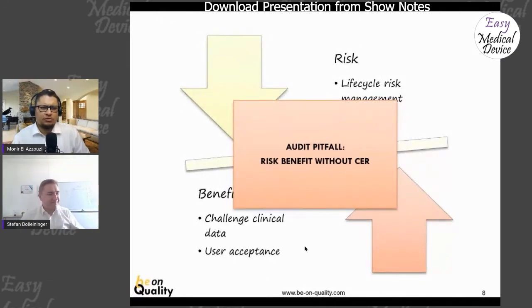Something to look at, because when you are reading the 14971, the risk management ISO, when you arrive at risk benefit, they say if you want to evaluate that, you have to go to the ISO TR 24971, which was like, what I'm doing now? I have the document, but I cannot do anything with that without looking at the other things. So now you can, and I hope it can help you for that.